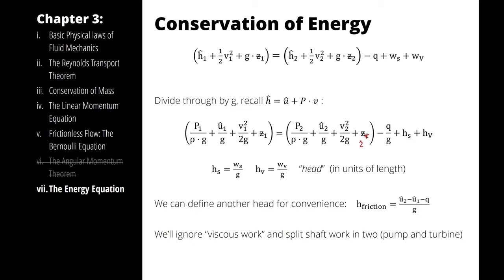The quantity of head, that's the specific work divided by gravity, is a way of kind of normalizing the specific work that allows you to keep track of it in one dimension. And that one dimension is useful when you're also talking about other quantities in one dimension, like how you can represent a pressure in terms of just a height of a column of fluid. So you might hear things like the pump head is 10 meters or something like that. Again, that'll make more sense once we start getting into examples with context.